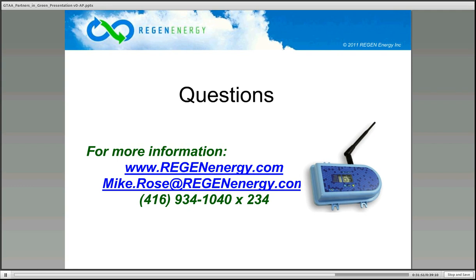When we install the system initially, we run it in baseline, set up the duty cycles, let it run for a bit, and do measurement verification, which is very important for getting your incentive money back. We run alternating days, controlled and uncontrolled, and get a nice set of data that we apply for your incentive. Throughout that whole commissioning period, we're making sure you're comfortable with where the building is set, and we won't leave you until you're happy with it. We also maintain the alerts, so if something's going wrong with your building, you'll be getting those alerts on an ongoing basis.